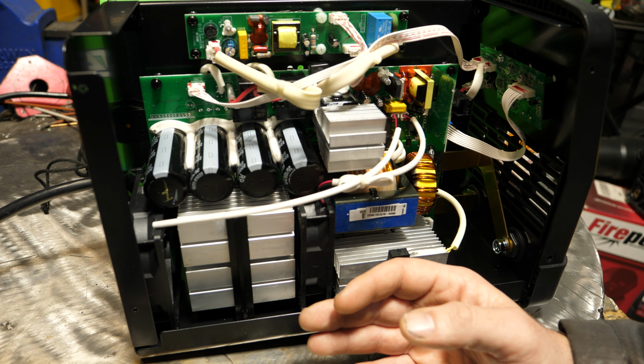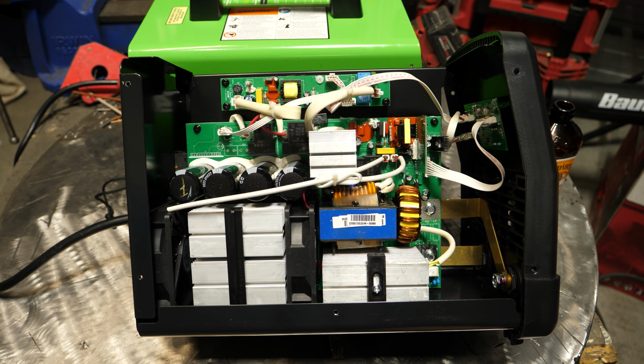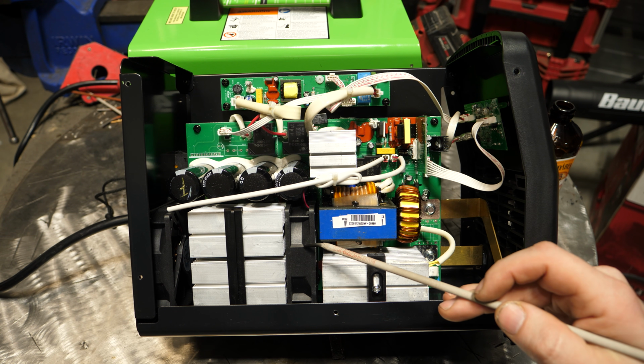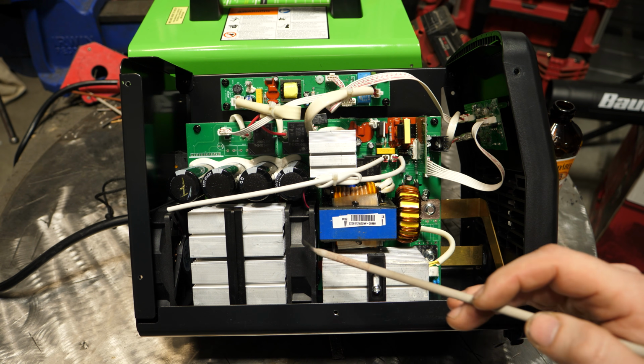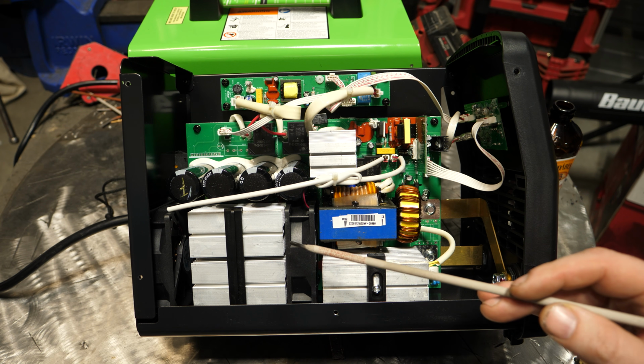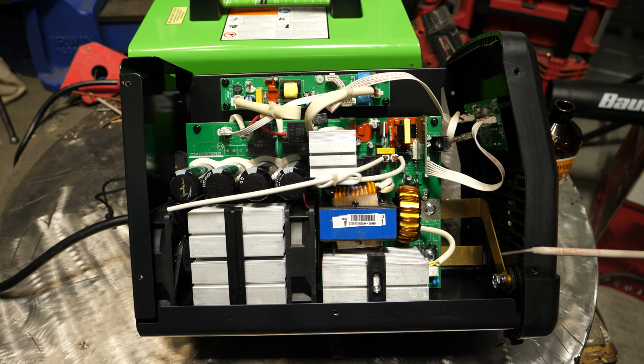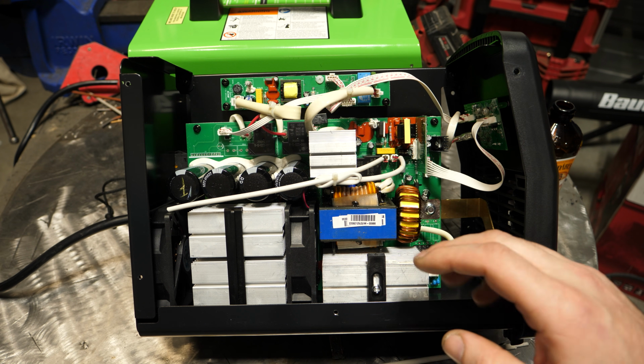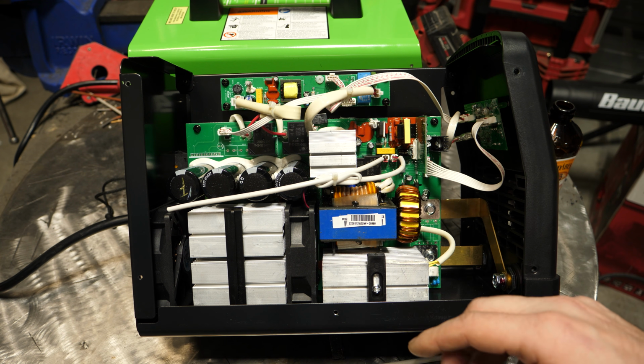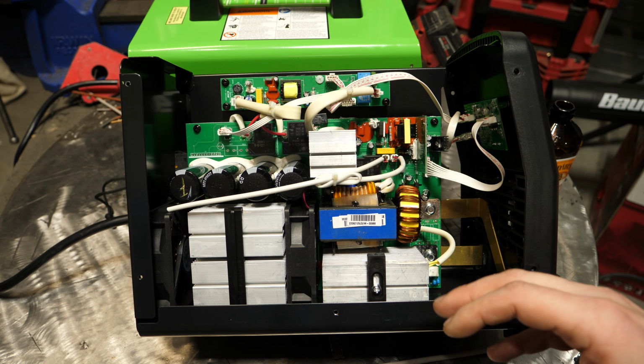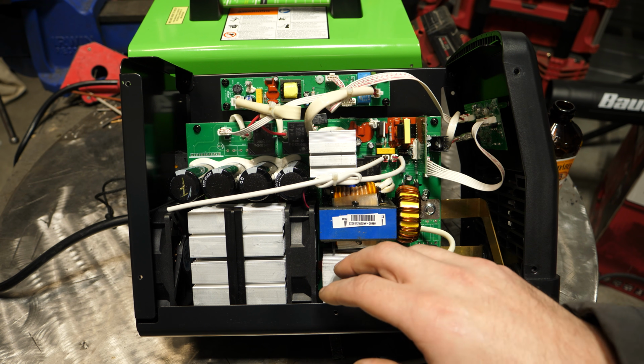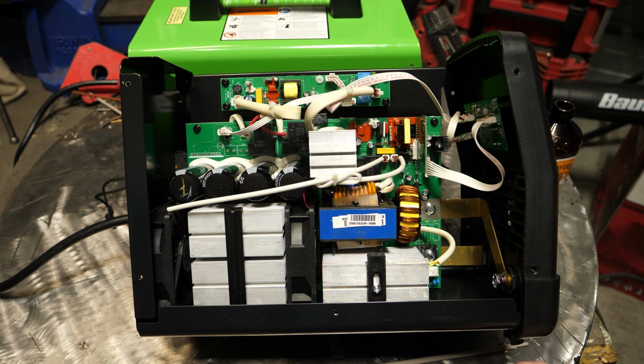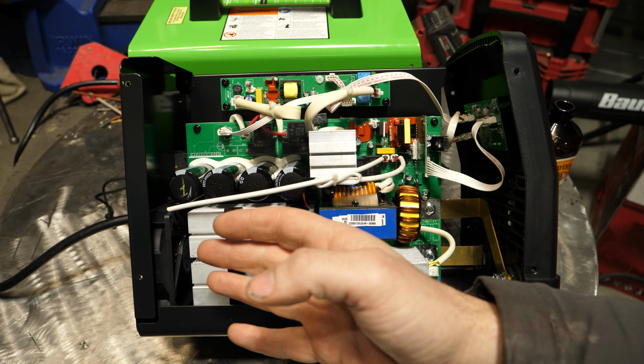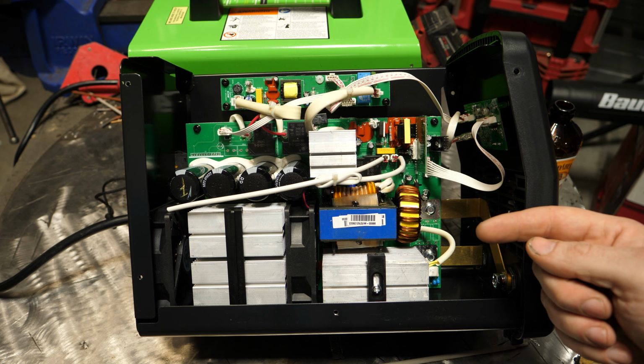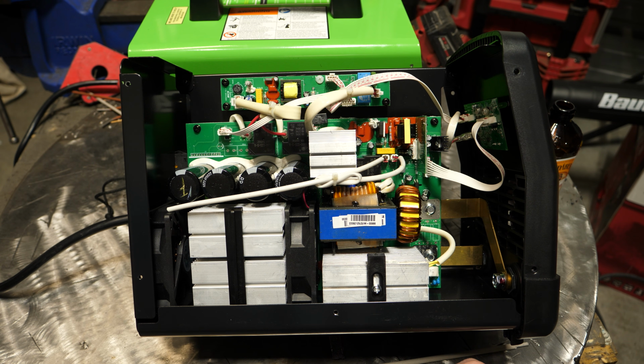Let's get into the meat of this. This uses conventional PC power fans, which is fine, and it uses 2 of them in a row. That's kind of smart because the air that comes in through here likely gets pushed out through the back. So the important components, like the IGBT modules, which are likely underneath here, or if it uses MOSFETs, whatever it has for that, and the bridge rectifier, which this likely has in here, all have decent, thick aluminum heat sinks, and the air pattern puts all the heat-producing stuff right in line of the airflow, so they probably won't get too hot.